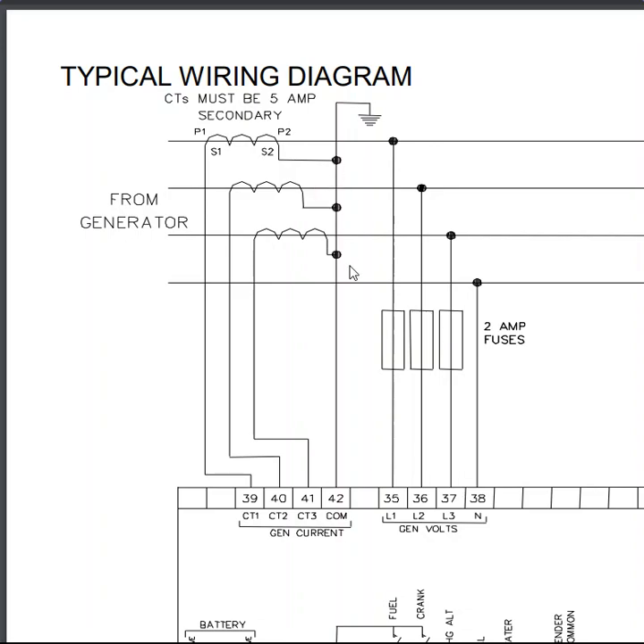And you're going to have one COM that is tapped off of all 3 of the wires going to ground, and then you're going to have L1, L2 and L3, one wire going off of each of those to 39 for L1, 40 for L2, 41 for L3. They must be a 5 amp secondary, so you're going to have a primary and then a secondary. It has to be a 5 amp secondary.